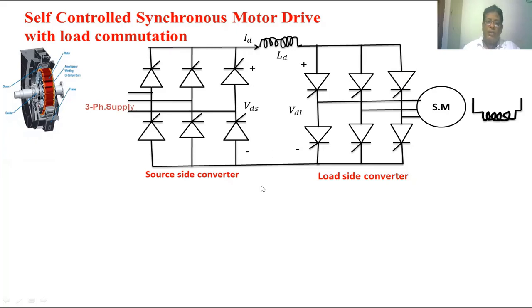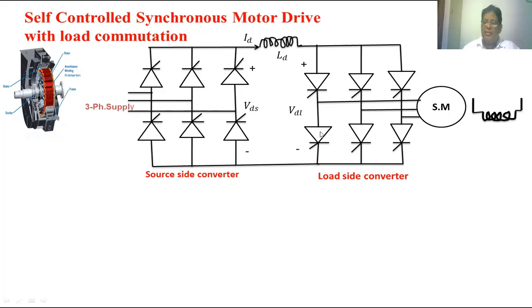Now we are going to see how exactly the power will be passing from the source to the load. The load is a synchronous motor. If we maintain the firing angle of the source side converter less than 90 degrees, then this converter will be acting as a rectifier, so the AC will be converted to DC. If we maintain the load side converter firing angle greater than 90 and less than 180 degrees, then this converter will be acting as an inverter. So the power will be passing from the source side to the motor.